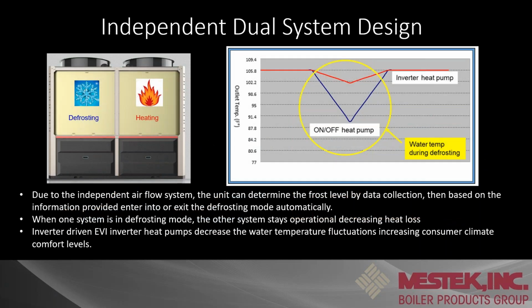Just to give you another idea how that looks, because we are independent, two modules independent, I could have one in defrost and one in heating. And that's the way it's going to work: okay, we need to go into defrost, let's do one coil, get it defrosted. And this will happen in a matter of seconds, how quickly they will defrost. Have that one switch over to heating, go to the next one, and put that one in defrost. So we're not completely out, and we don't need some type of backup to inject warm water into the loop when we are in heating.